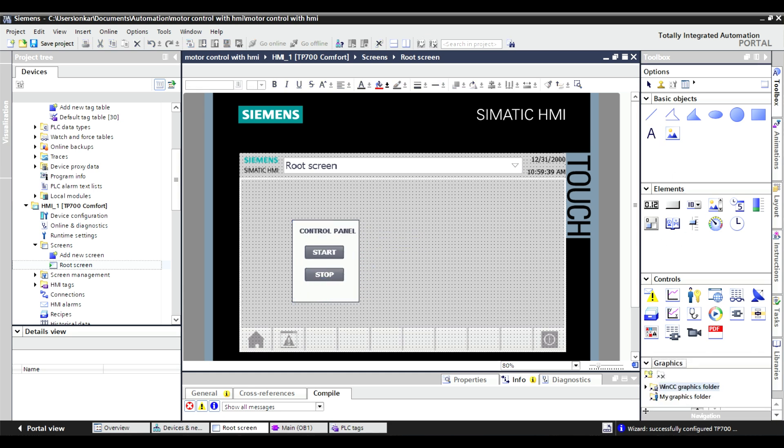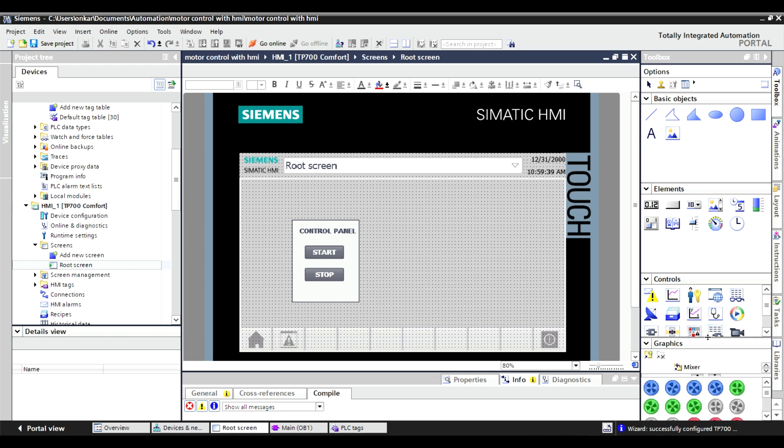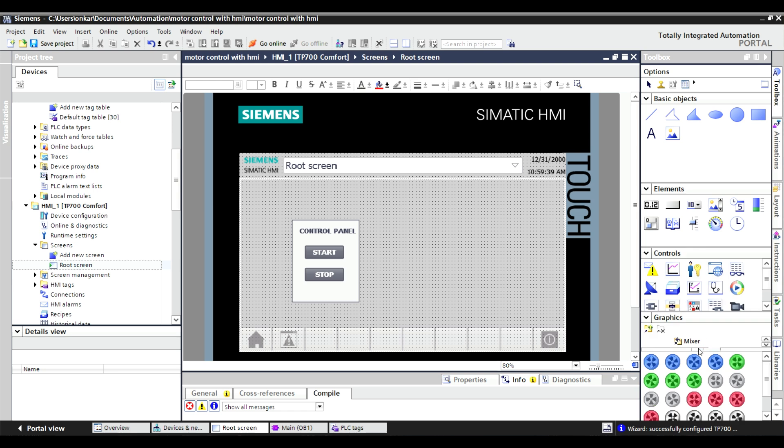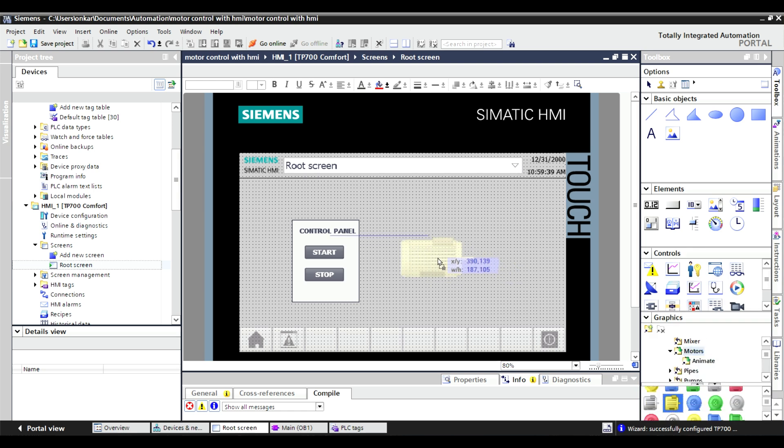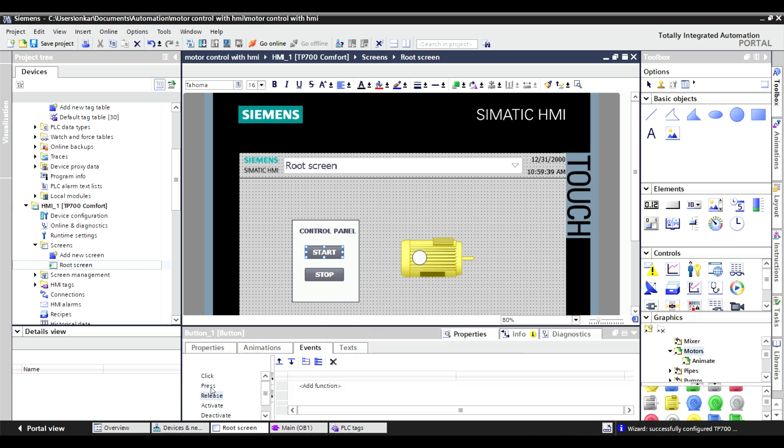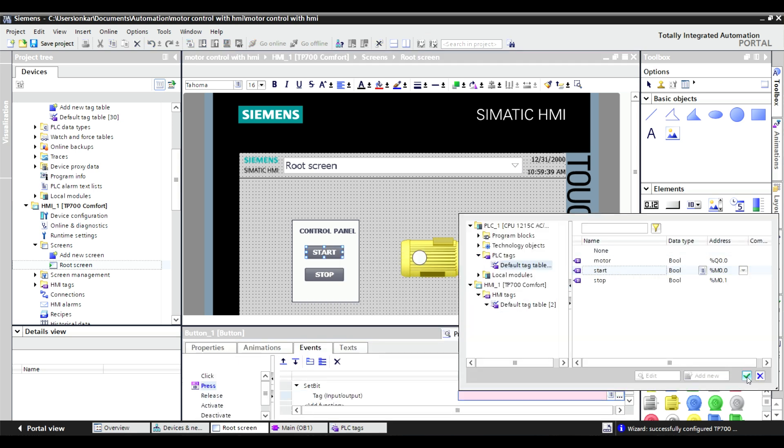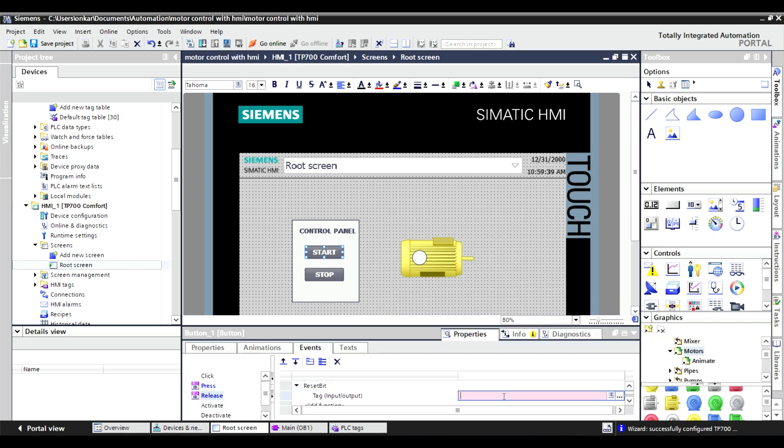Next, assign tags to the buttons. For the start button, add an event on press to set a bit for the motor tag, and on release reset the bit. Do the same for the stop button. Add an event to set a bit for the stop tag and reset it on release.